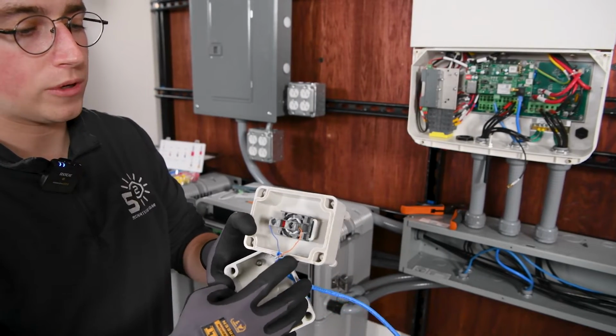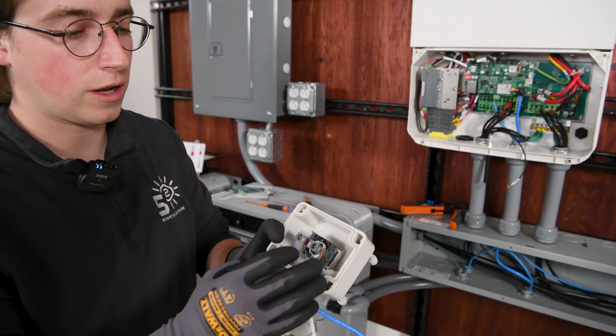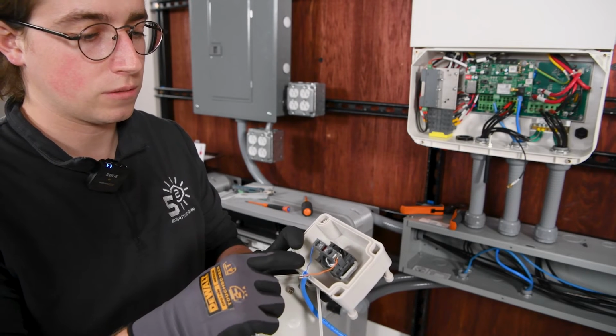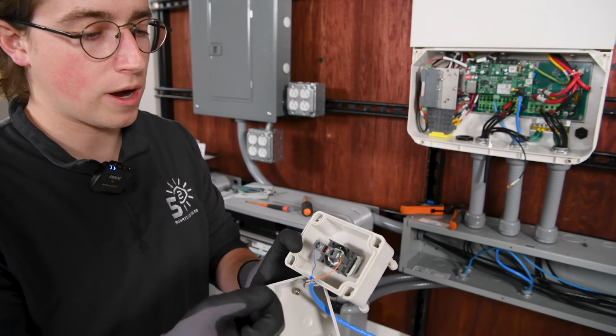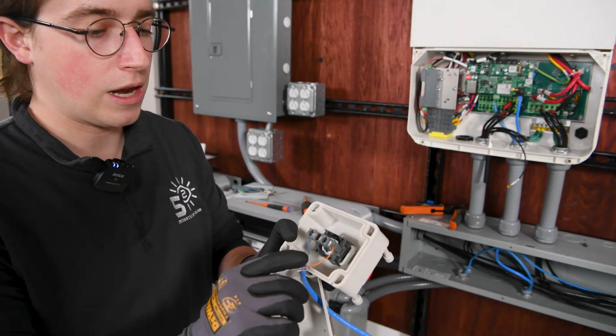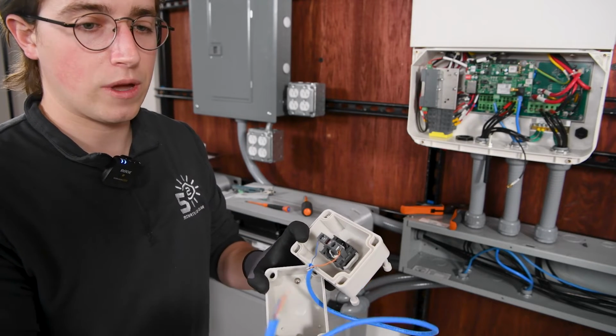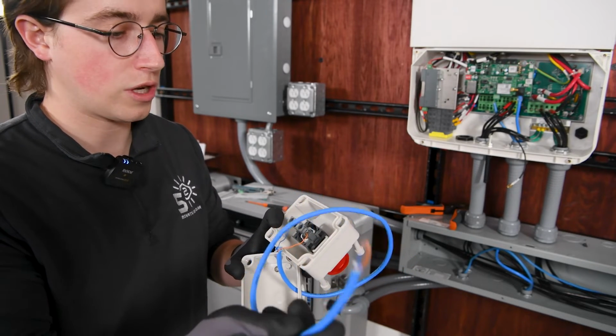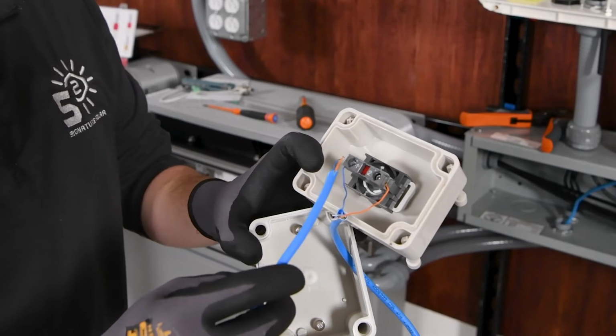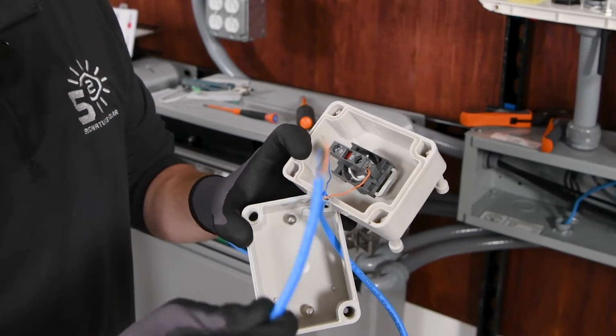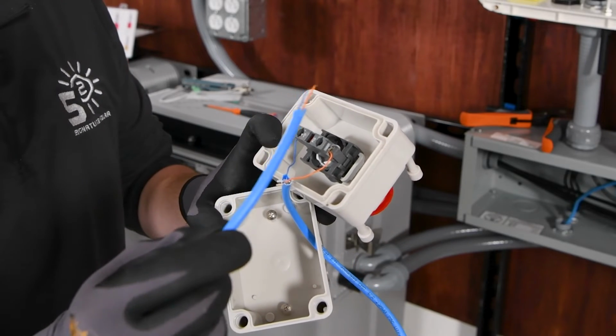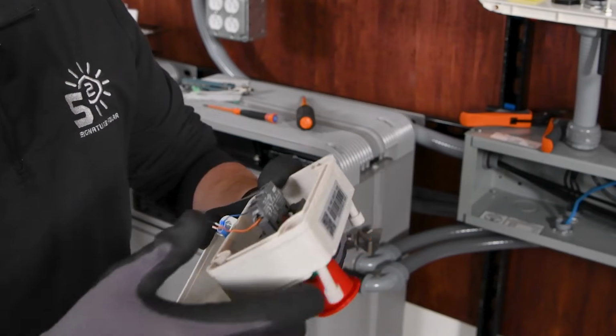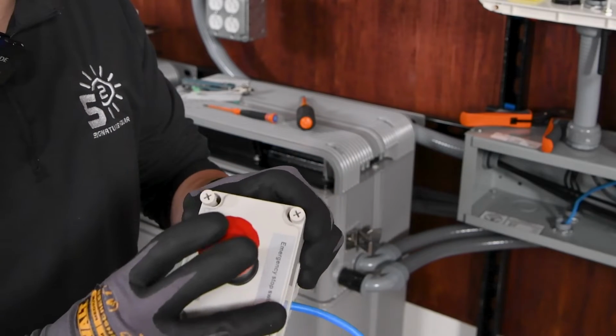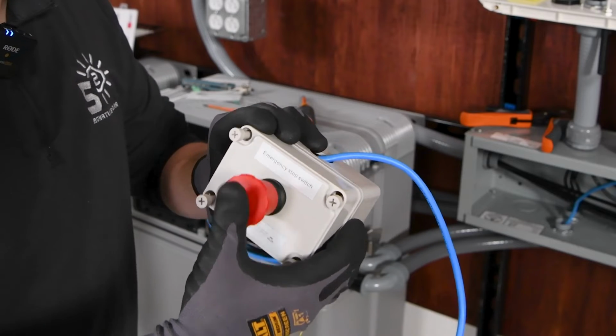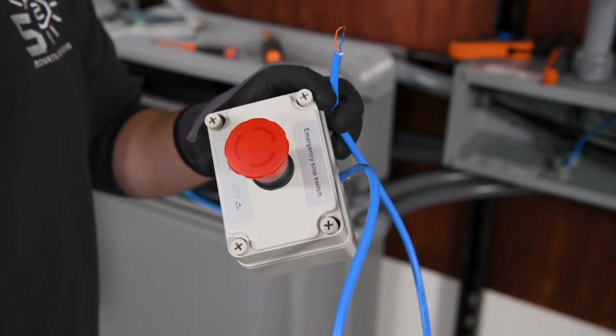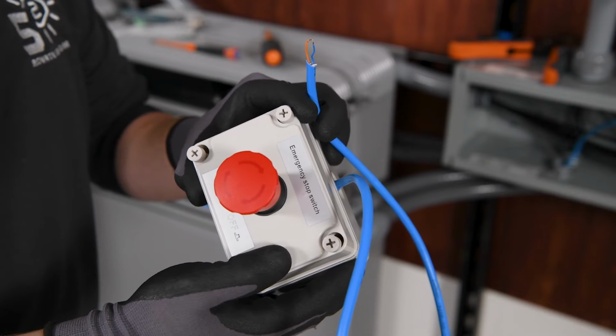To wire up the rapid shutdown initiator that comes with the Growatt 11.4, there's just 2 inputs. One is going to be for our blue wire, and the other is going to be for our orange wire. Now, when we go to connect to the 3-pin connector, we're going to connect the orange and blue wire the exact same way. All that we're doing is making sure that the circuit stays closed and that we have continuity across both conductors to keep the keep alive signal there. Once we initiate rapid shutdown, so we push our emergency stop button here, what we're doing is we're actually opening the circuit and no longer allowing the keep alive signal to flow between the 2 wires.